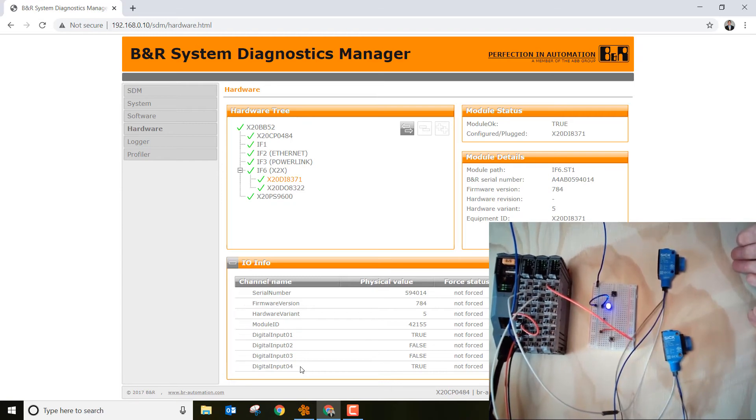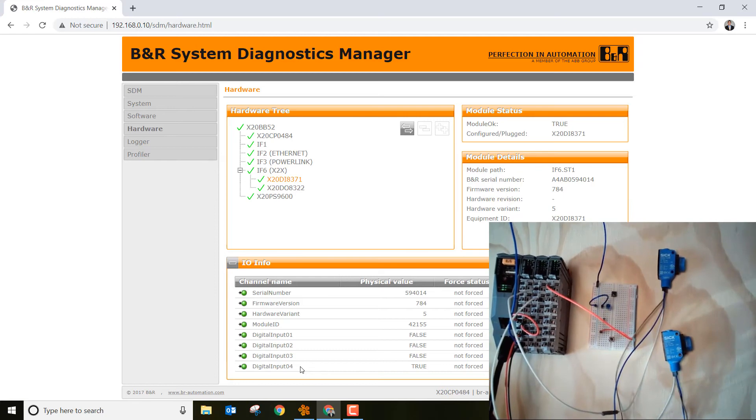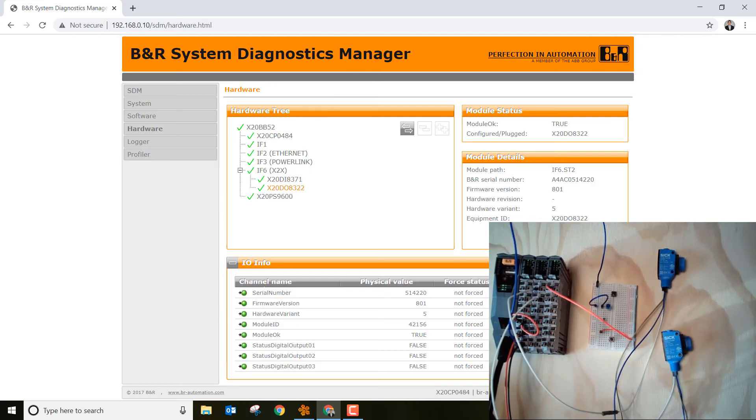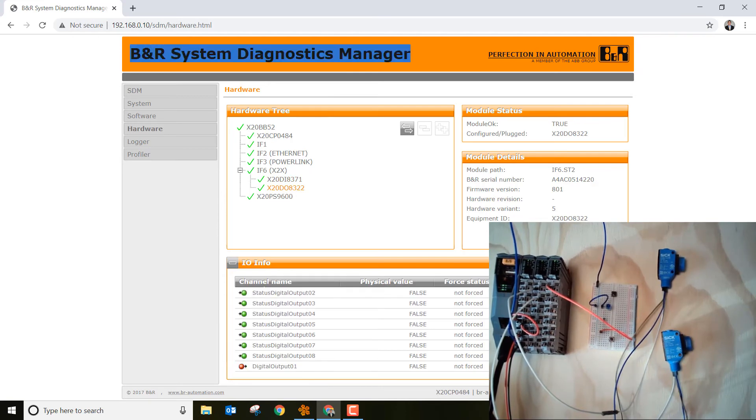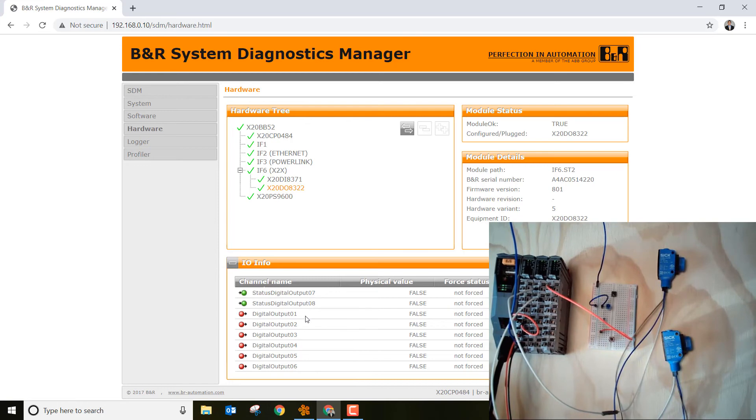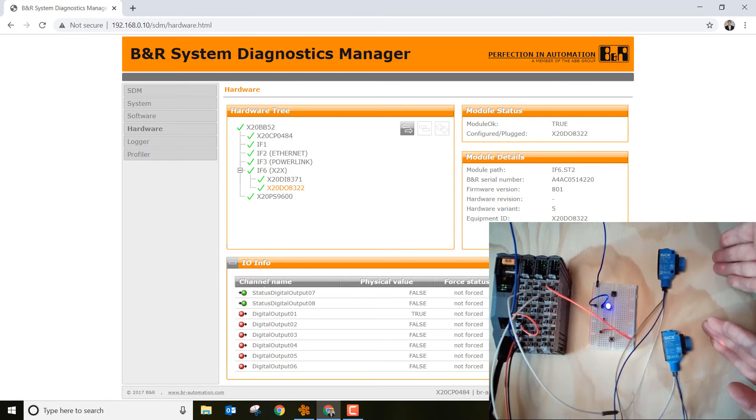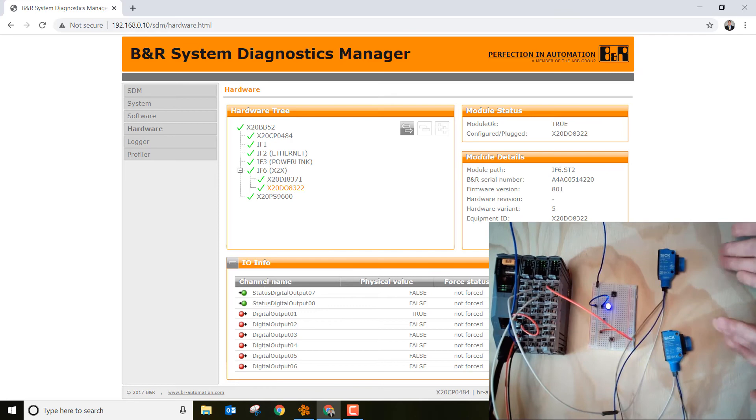Next, let's go to the X20DO8322 and then scroll down a little ways until we find the digital outputs. And remember, we're tied into digital output 1. So I'm going to block sensor 1 and sensor 2, and you can see that digital output 1 goes true right there on systems diagnostic management tool.